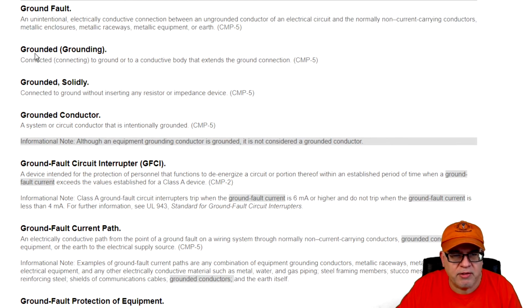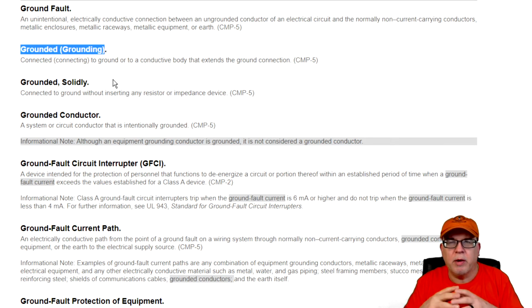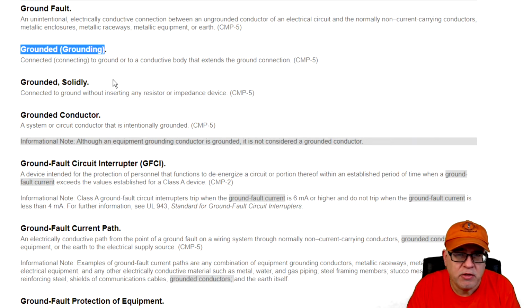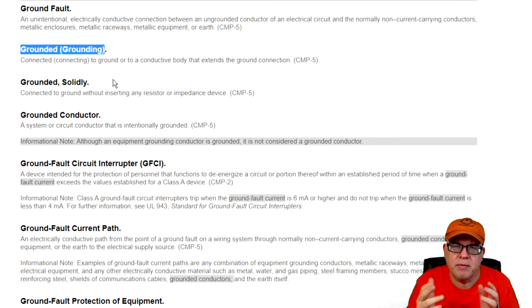The next one, we obviously fundamentally need to know what grounded is. When we're grounding something, or we're making an act of connecting something to ground, once it's done, it's considered grounded. So when we say a grounded neutral conductor, for example, back at the transformer at the XO, it's a connection that's made to the earth, and at the transformer the neutral is now grounded. In that case you always have a grounded conductor. You don't always have a neutral. It depends on the system, and it has to do with the measurements and whether or not you have a grounded system. We'll talk about that when we get to that level.